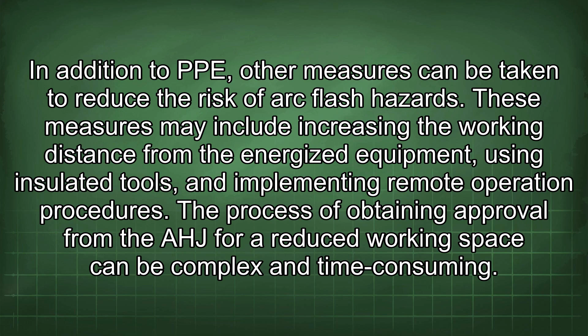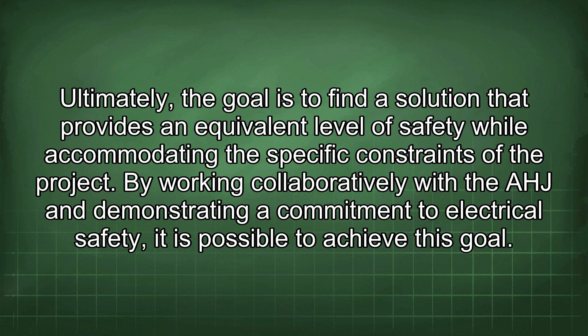The process of obtaining approval from the AHJ for a reduced working space can be complex and time-consuming. It is important to start the process early in the project and to work closely with the AHJ to ensure that all requirements are met. This may involve attending meetings with the AHJ, providing additional documentation, and making modifications to the proposed arrangement as needed. Ultimately, the goal is to find a solution that provides an equivalent level of safety while accommodating the specific constraints of the project. By working collaboratively with the AHJ and demonstrating a commitment to electrical safety, it is possible to achieve this goal.